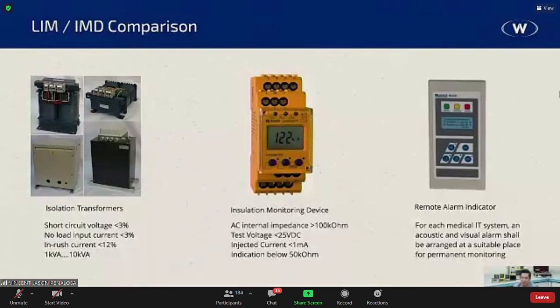Here, with the hospital insulation monitoring device, anything below 50 kilo ohms is a fault to them. All right. Okay, and then you have what we call the remote alarm indicator, right? That's the one that's showing up in your OR theaters, and that's the one that's giving out the alarm. In fact, that particular device can also accept 12 channels of dry contact inputs, also for alarms of, let's say, oxygen or whatever gases that you might have that have sensors on them.